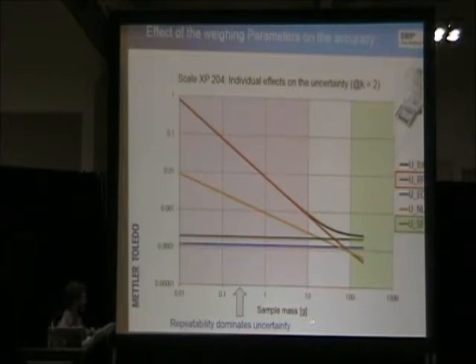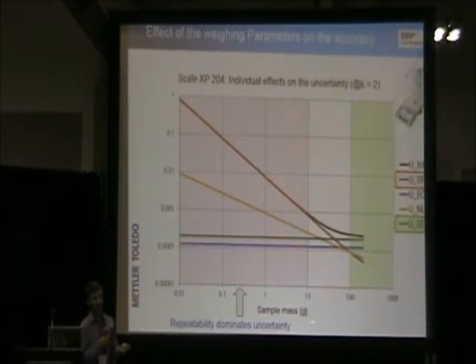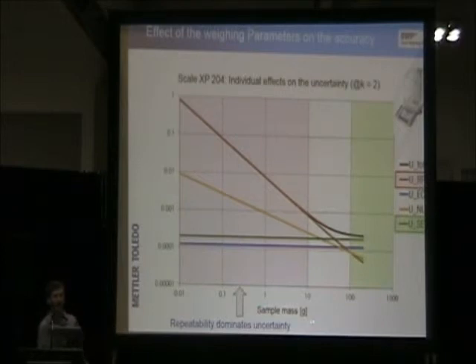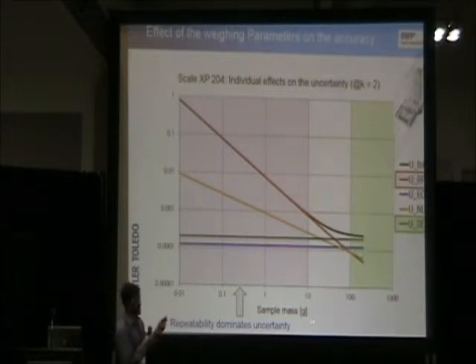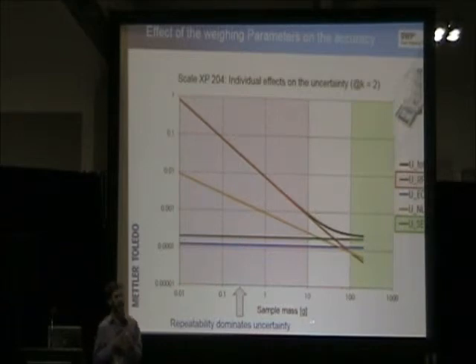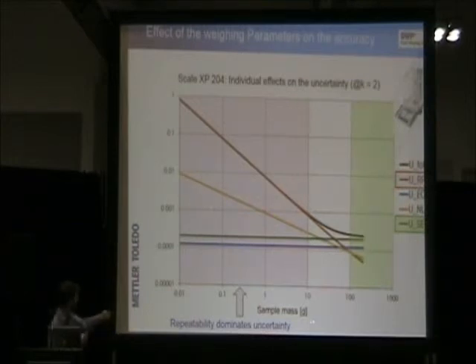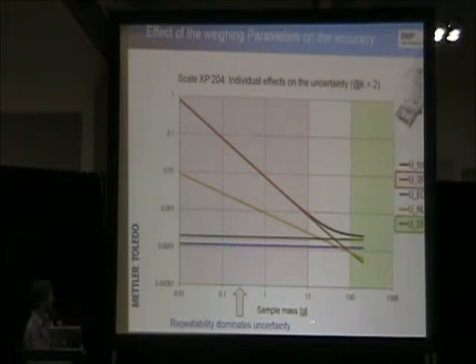As you can see here, this green line is sensitivity. Sensitivity is closest to the uncertainty of measurement near the capacity of the instrument. What I mean by that is sensitivity has the most effect on your uncertainty of measurement near the capacity. This is why when you do a routine test, you want to test near your capacity. It's common practice to test near where you're actually weighing, let's say 30 milligrams, when in reality you should be testing right here, which is very far apart from your total uncertainty.